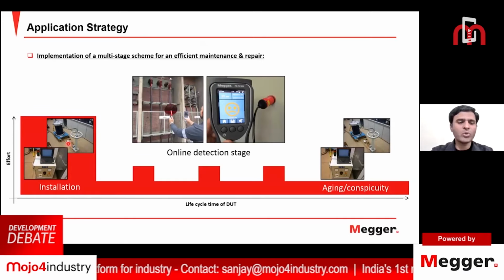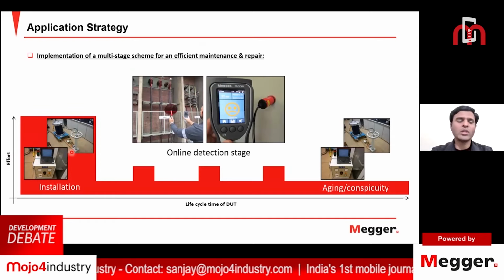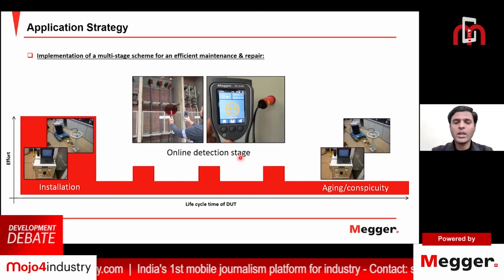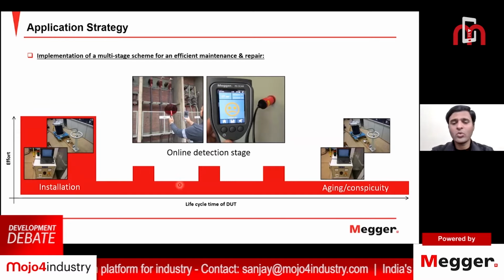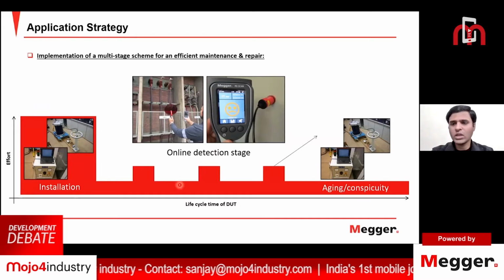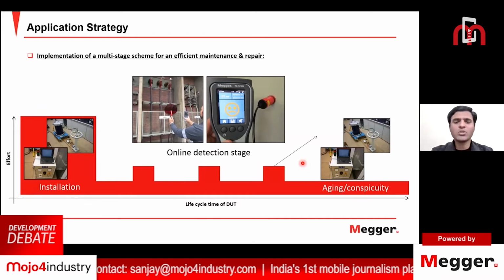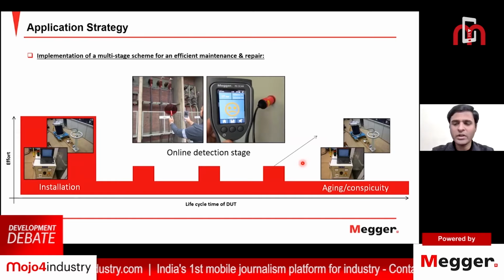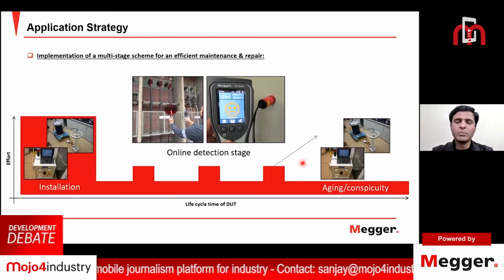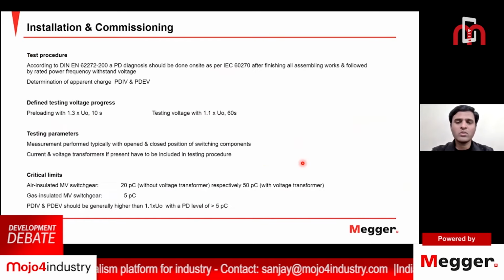Before putting a particular asset into service, at the installation time, an offline measurement can be done to ensure that there are no discharges in that asset. Once the asset is put into service, online PD detection can be done to understand its condition and identify whether it is deteriorating or not. And once it is approaching its life cycle end, we can take a shutdown and do the offline PD measurements to get the detailed measurements. If there are any particular components in that asset which are highly degraded, you can just replace or repair them. This will help us to use that asset for the maximum life period which it is designed for.